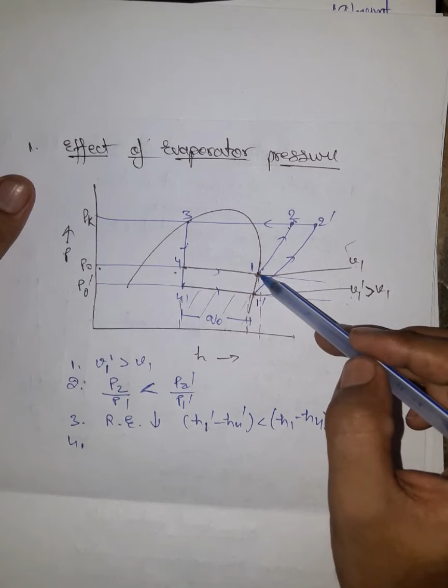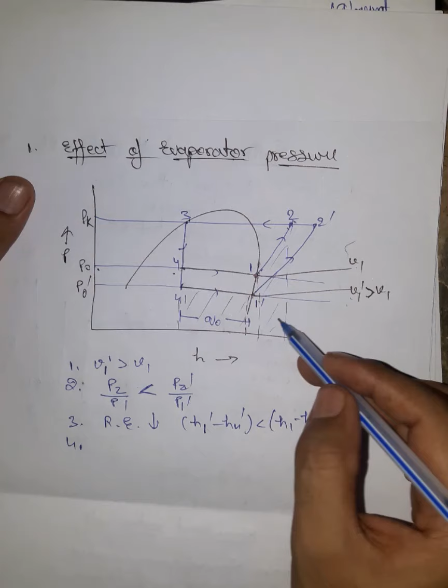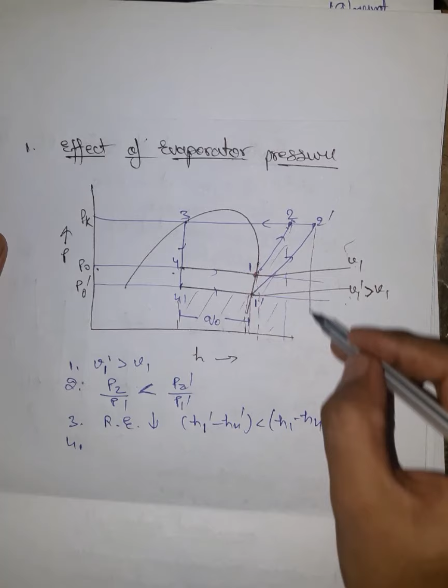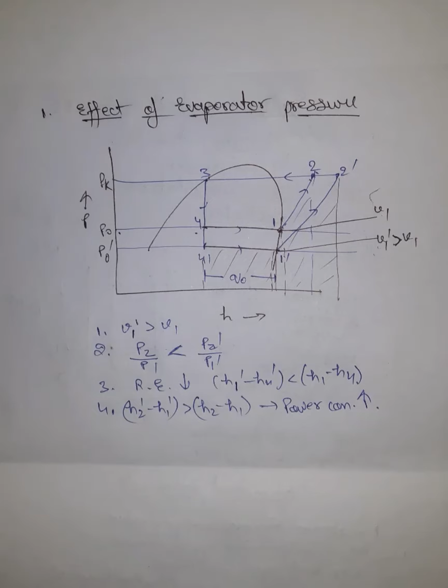Now we talk about the power consumption. Power consumption is the work or amount of energy needed to drive the compressor. How can it be calculated? H2 minus H1 for the original case. You can see in the diagram that it is only this region, but for the lowered evaporator pressure it goes from here to here, so it has increased. We can write that H2 dash minus H1 dash, the power needed by the compressor after lowering the pressure, is greater than H2 minus H1, the original power required. That means power consumption increases.